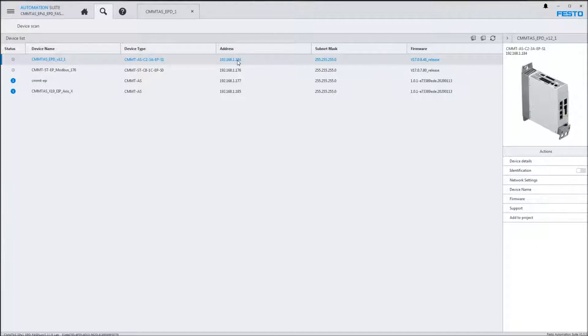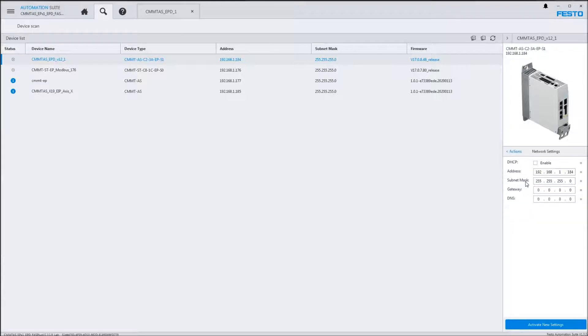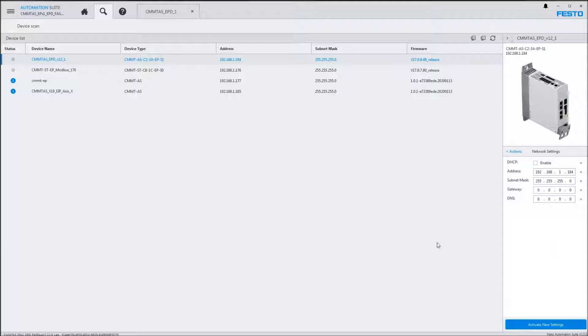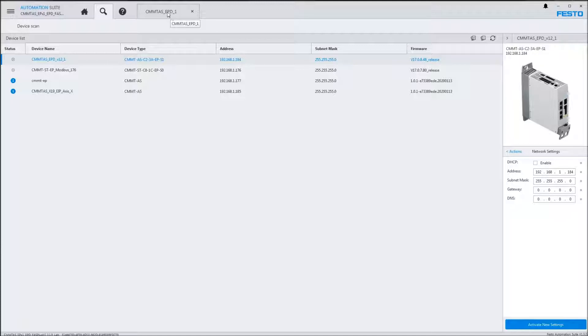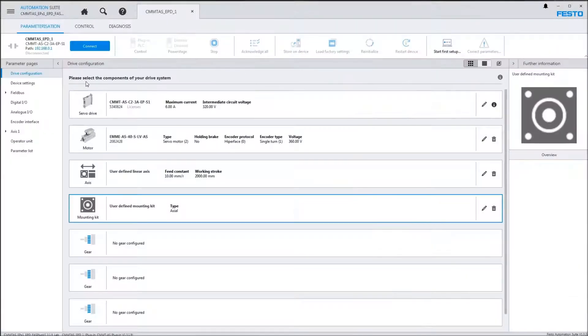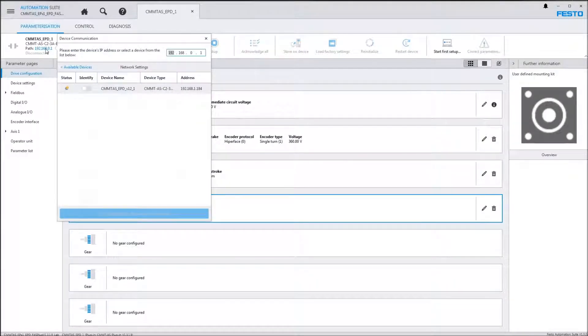The alternative is to go back to our device scan tool over here. You click on the device, you click over here on the right for network settings, and you would modify the settings and then say activate. It might require a reboot. Typically once some of the communication is changed, it's going to ask you to reboot or it will do it automatically. Long story short, you come in here when you're finished and you select your device.